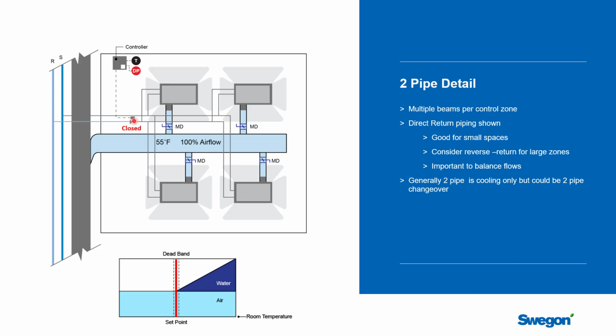Once this valve opens, and if it was 1 GPM per beam, and this valve opened to 4 GPM, you'd want to make sure that roughly each one of these beams sees 1 GPM, and reverse return piping will help you do that. Now this can only do cooling because it's a 2-pipe system. In theory, you could do a 2-pipe changeover and at some point switch from chilled water to hot water. Seems like a very rare application in chilled beams to do that.